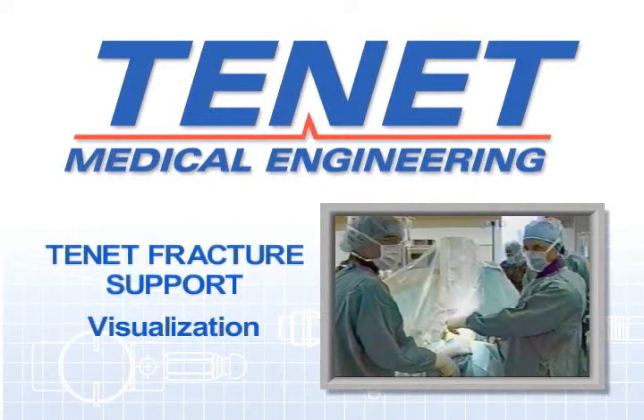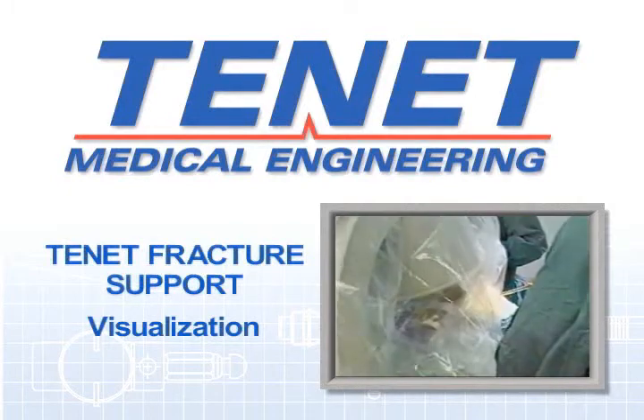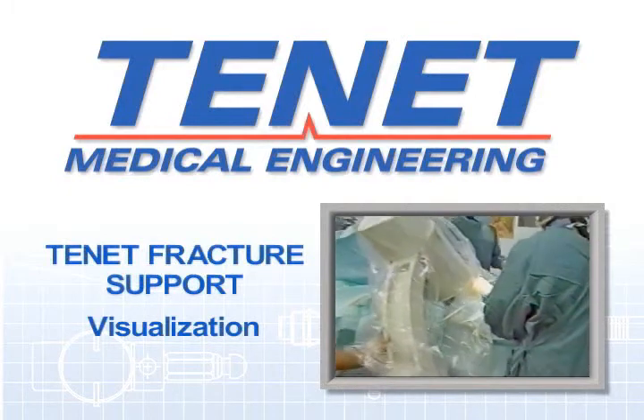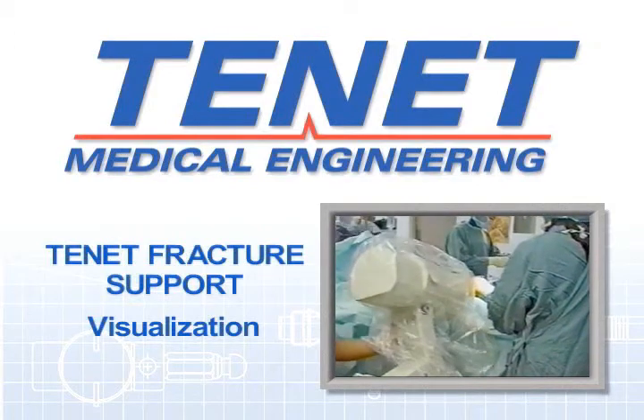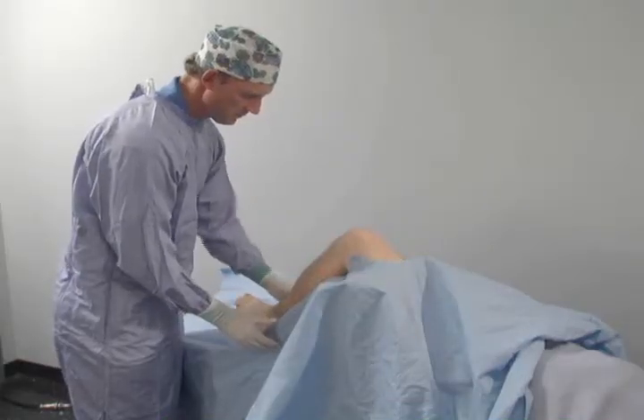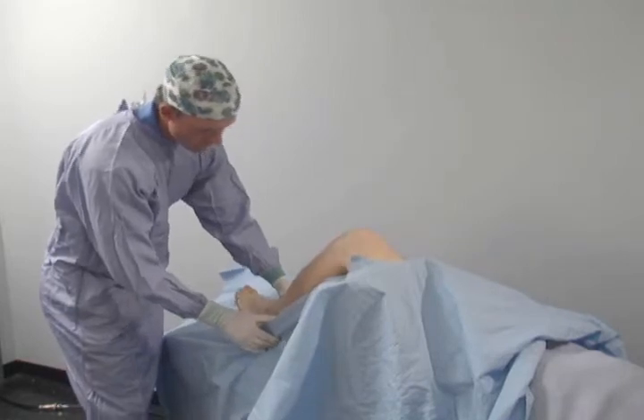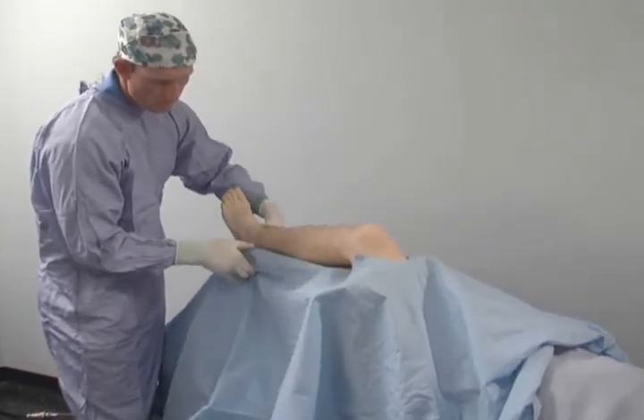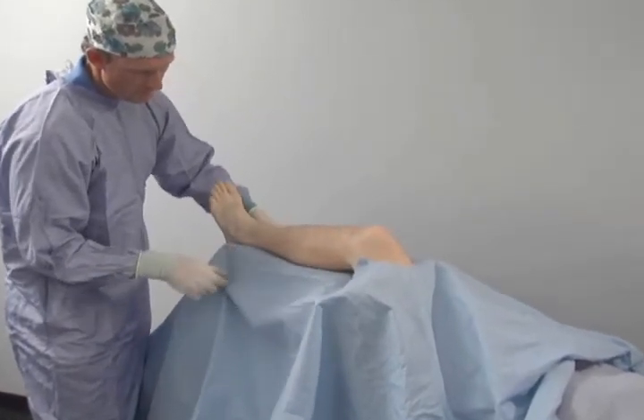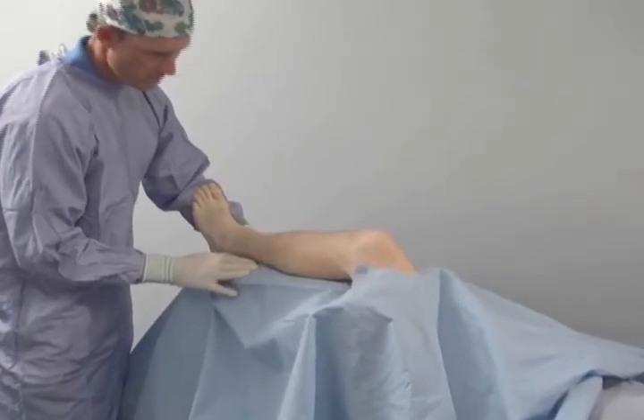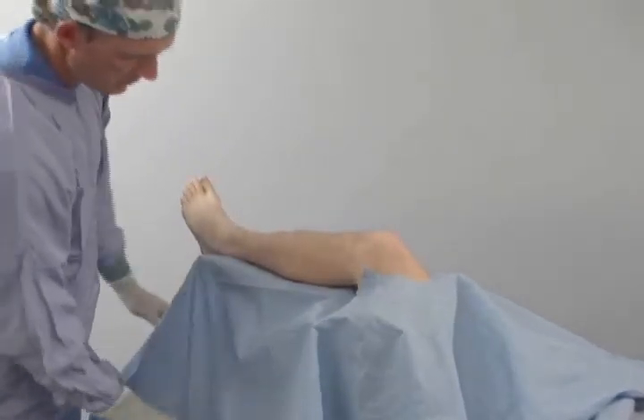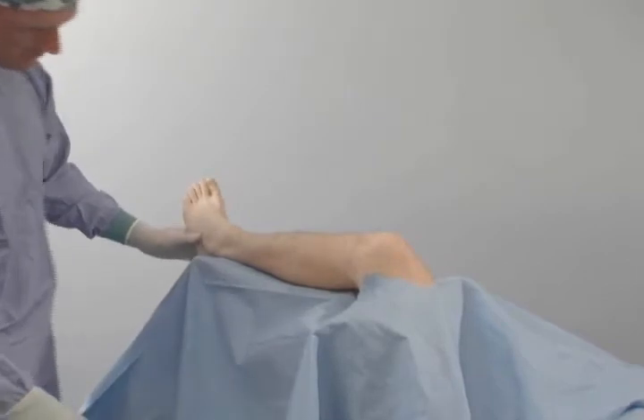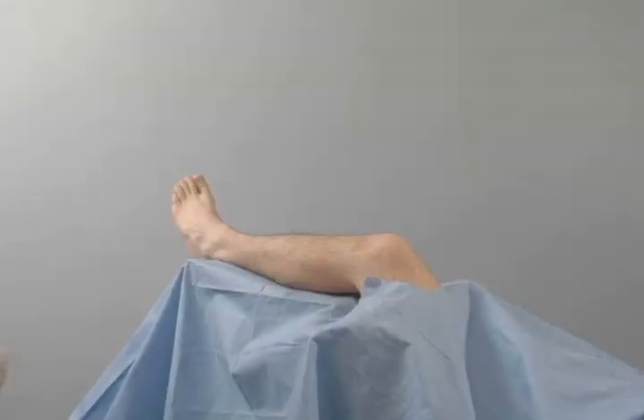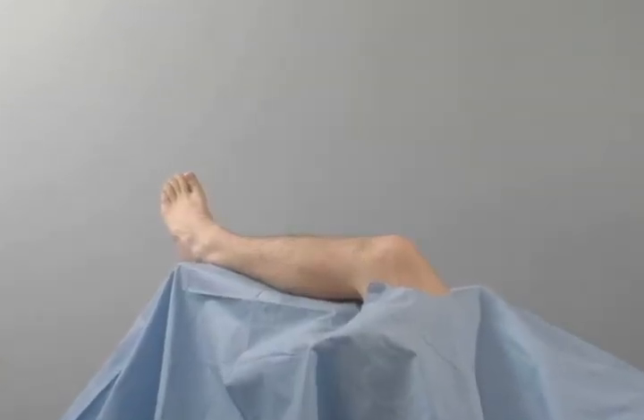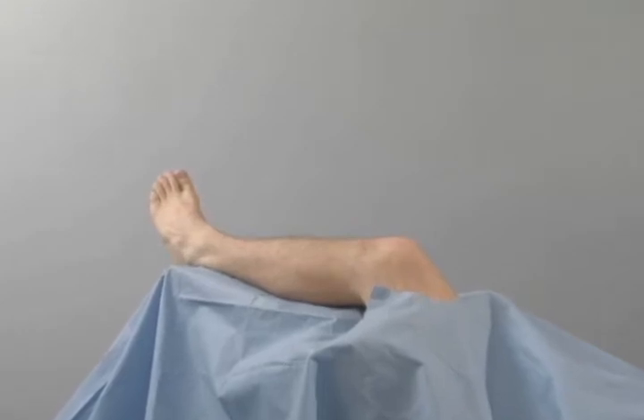Along the axis there is 12 inches of material that the C-arm is shooting through. Adjusting the view slightly will remedy this problem. After the nail is inserted, the tibial platform and tibia are lifted through the drape so that the tibia and platform are parallel to the OR table. Ensure that the leg is parallel and firmly seated in the grooves on the base. This position allows the C-arm to be positioned and provide the right angle when trying to get the perfect circles when lining up the distal screw holes.